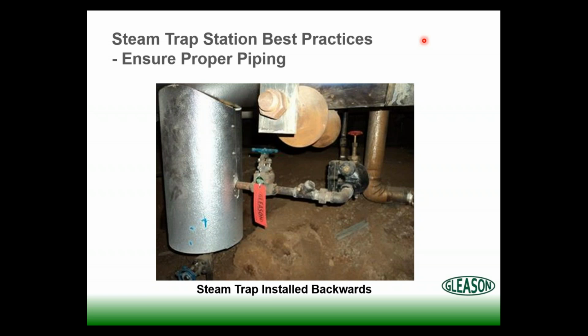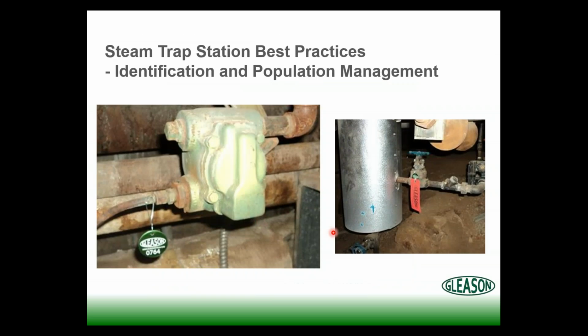Here's an application. Another best practice is to make sure they're installed properly, in the right orientation. This particular float and thermostatic steam trap is installed backwards. We're coming off the drip leg here, and they're coming into the wrong portion of the trap. So we won't get into that, but you see we tag that with a red tag to say, hey, this steam trap definitely needs some attention. So let's pay attention to proper piping of our steam traps.